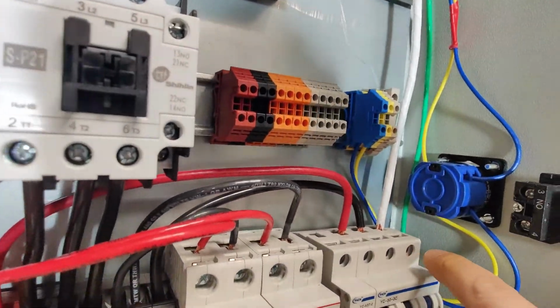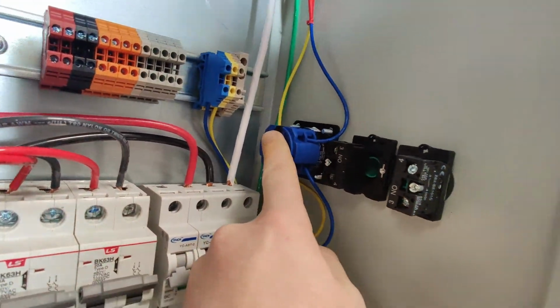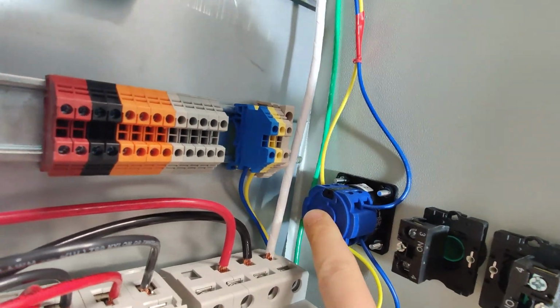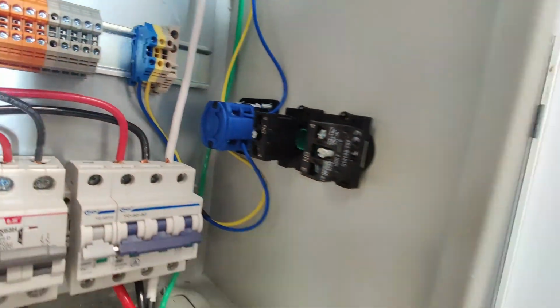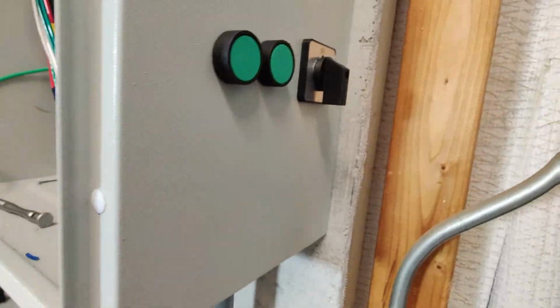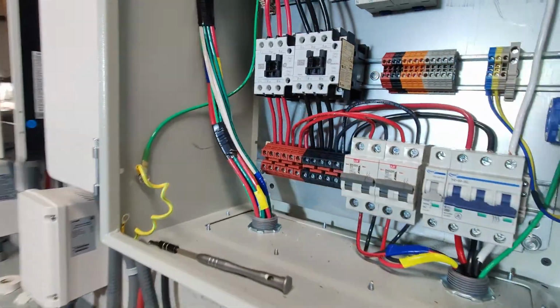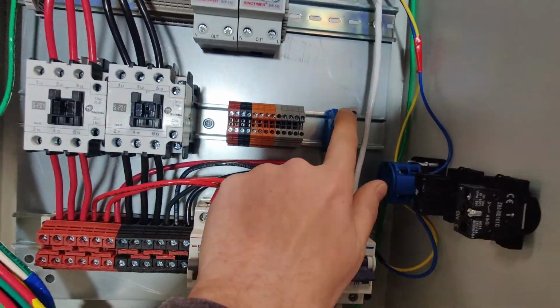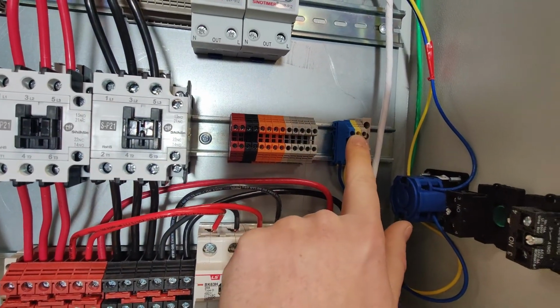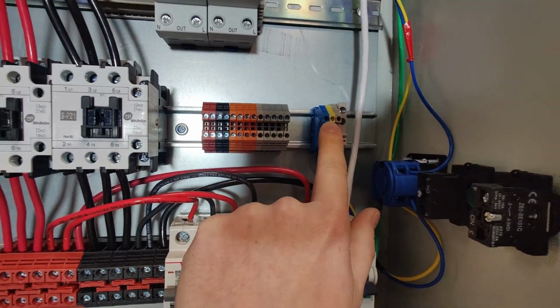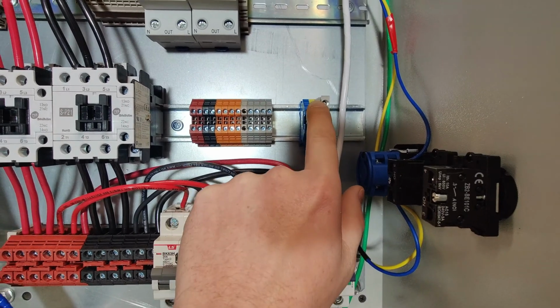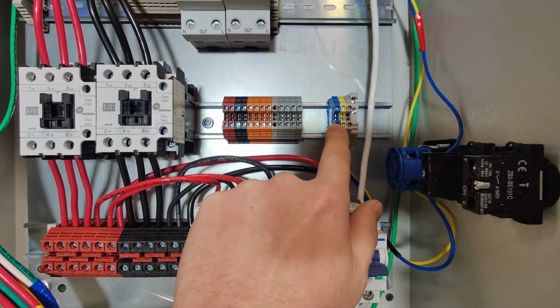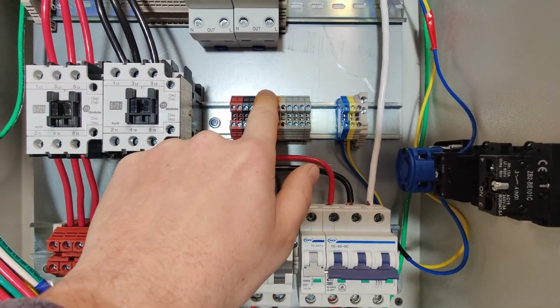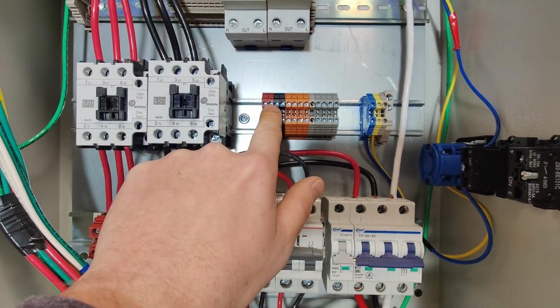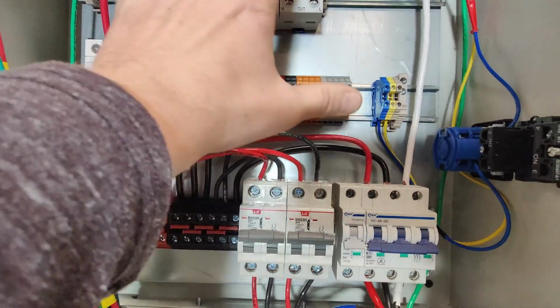And it comes into the back side of the switch, and we're switching both of those hot legs. We're switching the yellow and the blue wires with our on-off switch. And with that, what that enables us to do is we can switch this terminal block right here on and off. And what we're going to end up doing is we're going to take the power outputs from this terminal block here, and we're going to run them into these terminal blocks down here, and these terminal blocks down here are going to turn all these things on or off.